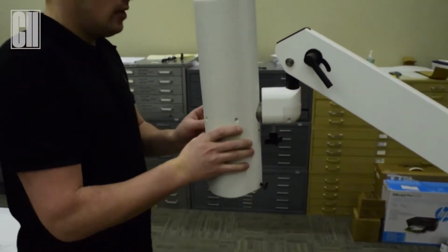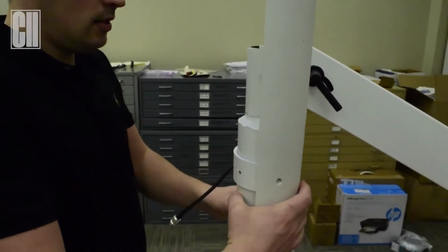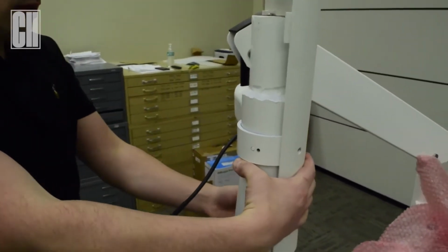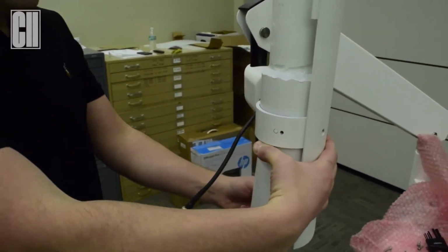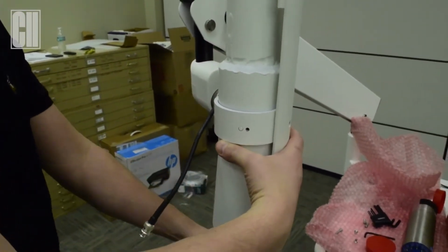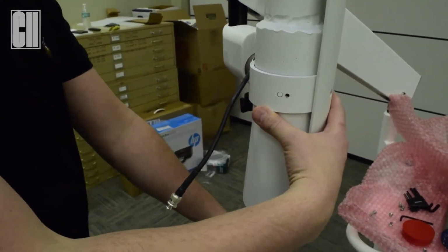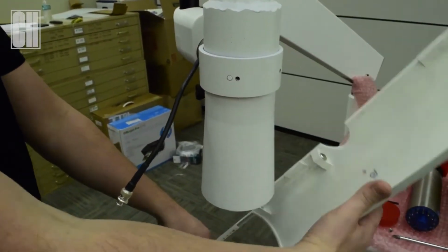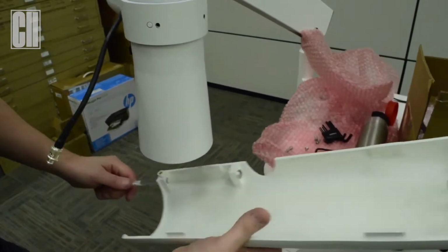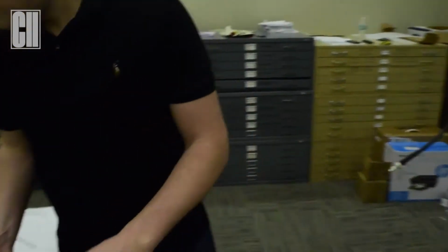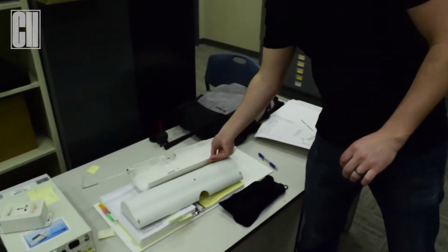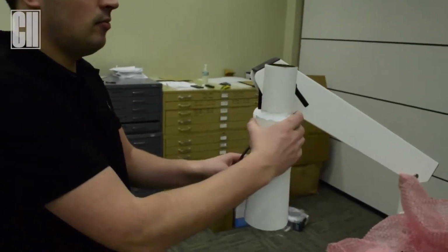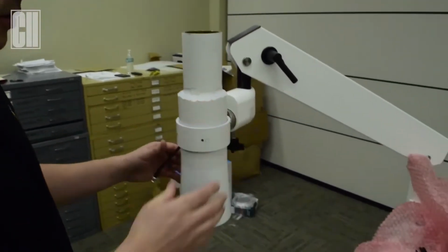Now when you remove this piece, inside you want to loosen the screw that's holding the pointer rod, and then you need to slide down the pointer rod past the holding so you can remove the casing. Place that to the side, and now we're ready to insert the detector.